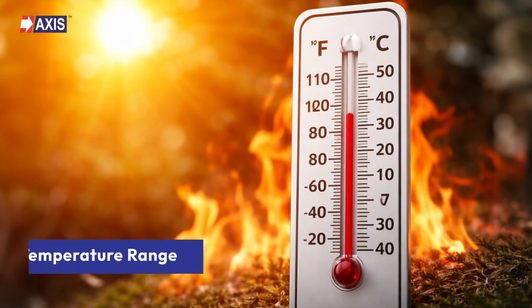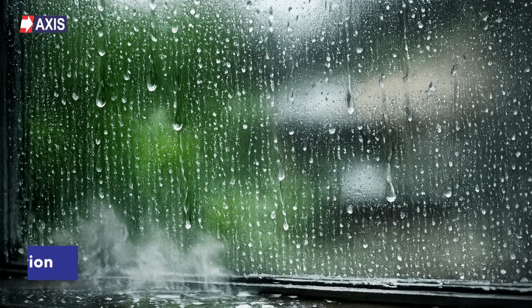Now let's check the temperature range. What is the minimum and maximum level at the site? The material must withstand operating and ambient temperatures. If the heat exceeds the rating, the material will soften, deform, or lose insulation strength. Then let's evaluate humidity and condensation. In humid areas, moisture can enter small gaps. If the sealing is poor, this can lead to corrosion and leakage current. Lastly, don't forget to check pollution and dust levels. In industrial or coastal areas, contamination can settle on the surface. If there is voltage stress, this can lead to surface cracking.